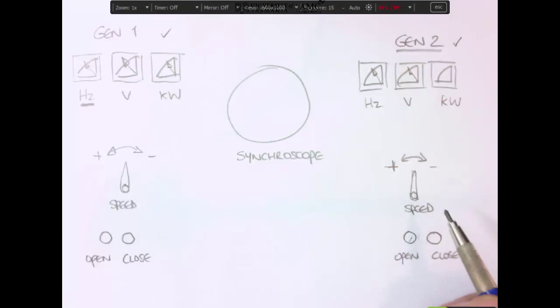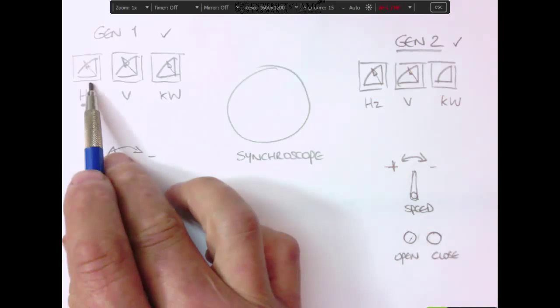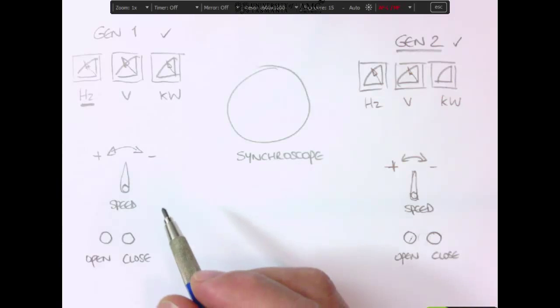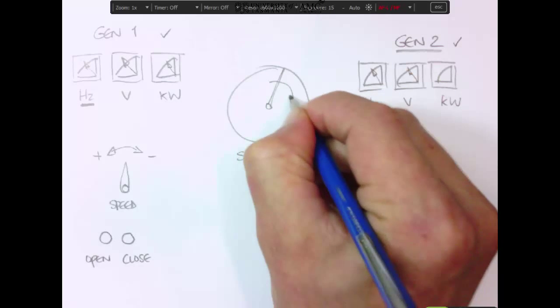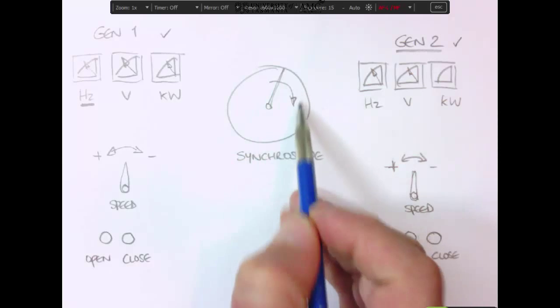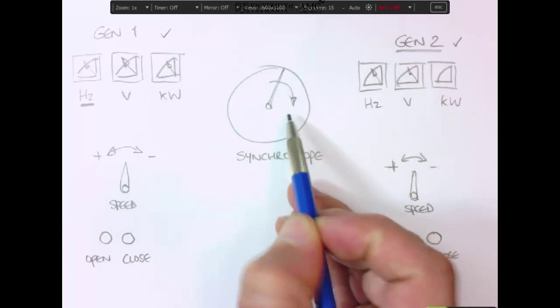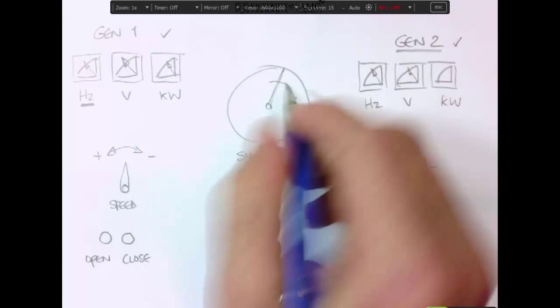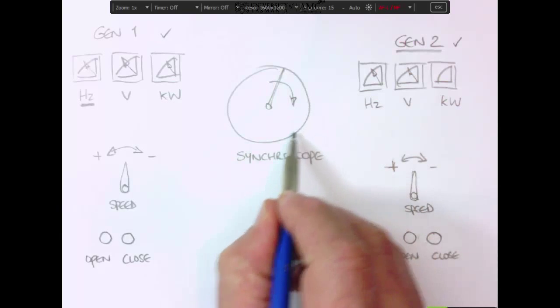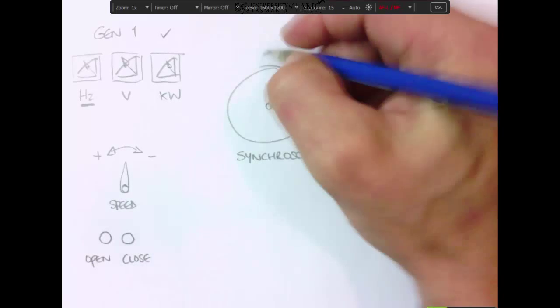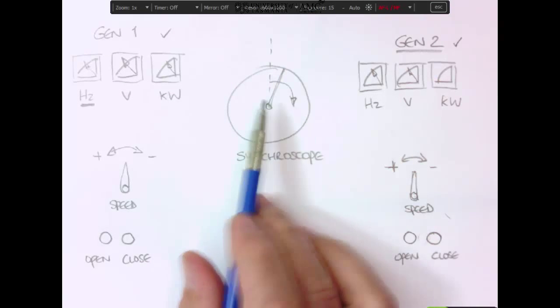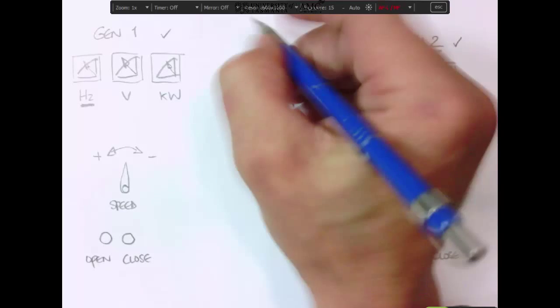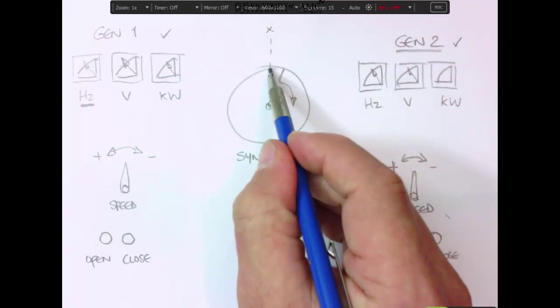Now, when we're synchronizing manually, what we want to do is increase the speed of our incoming generator just slightly above the speed of our onboard generator. And what that will do is get our synchroscope needle, which works like a clock dial, to start rotating clockwise. If the incoming is slightly faster, it will rotate clockwise. If it's slightly slower, it'll be anti-clockwise. We want it going in the clockwise direction and slowly. The point at which our generators will be parallel, or in sync, will be at the 12 o'clock position. So we want the needle to synchronize at exactly 12 o'clock.